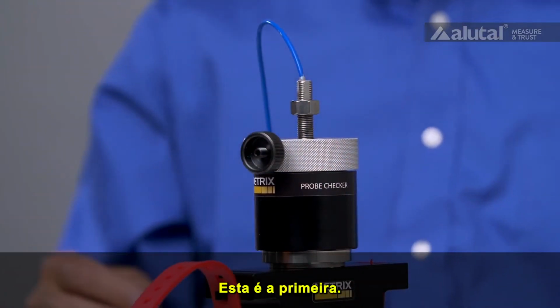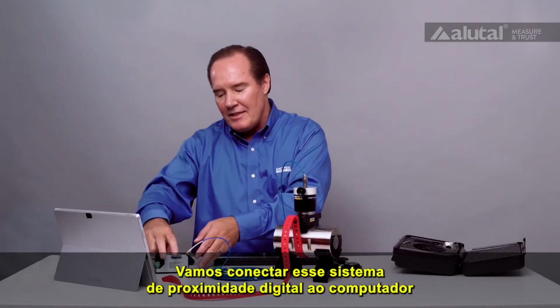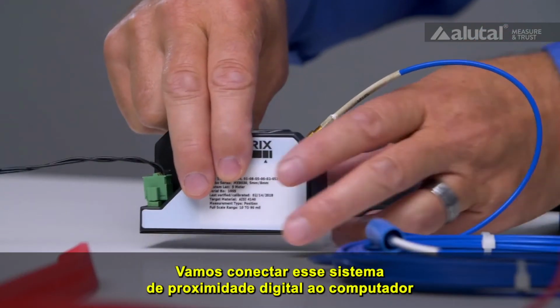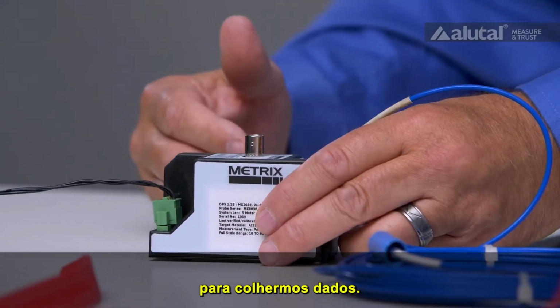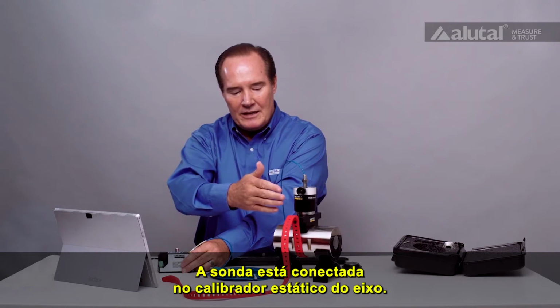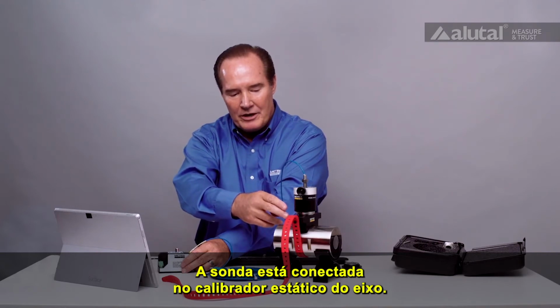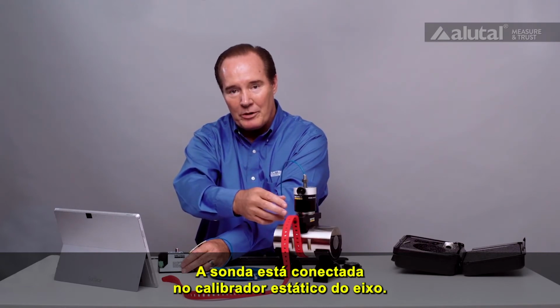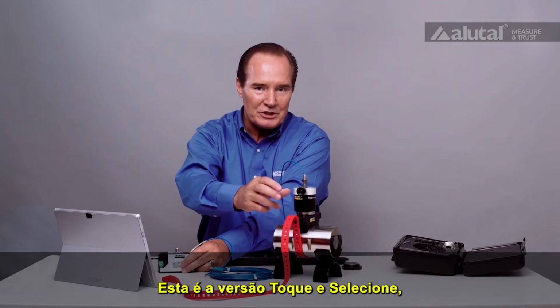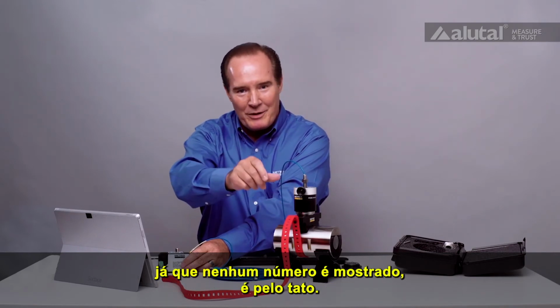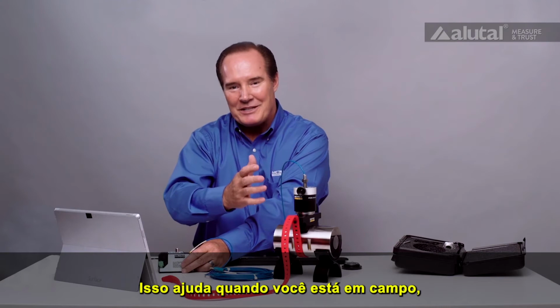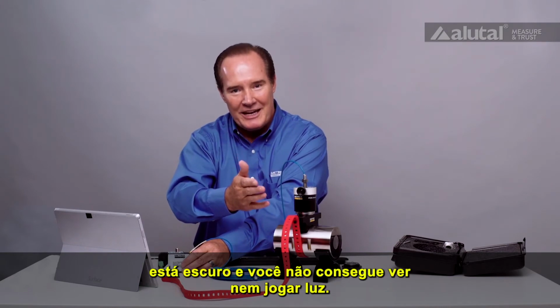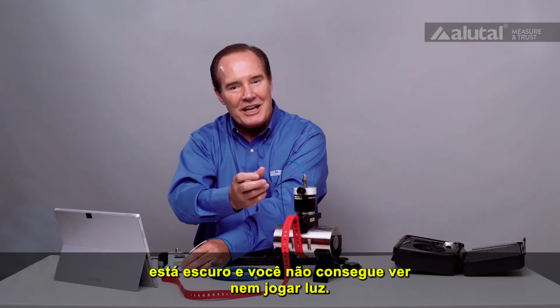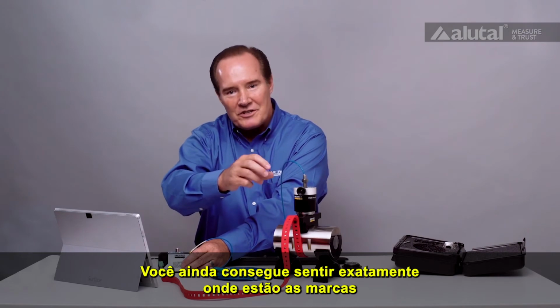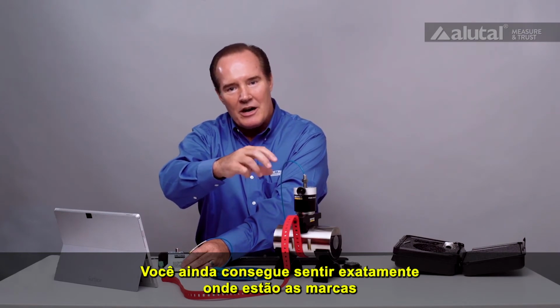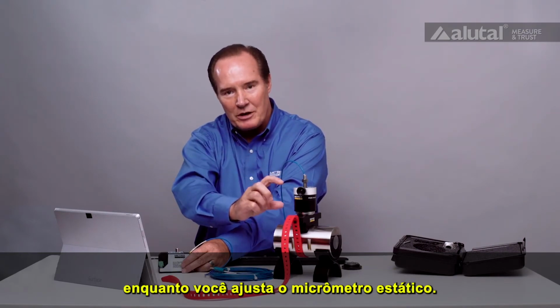That's the first one. Okay, we're going to connect the digital proximity system to the computer so we can take data. So we have the probe set in the static calibrator for the shaft, or the shaft static calibrator. This is the touch select version because there's no numbers coming out of here. It's by feel. You can do that. And it makes sense when you're on site, when it's dark and you can't see and it's difficult to get light in, you can still feel for exactly where the indents are as you adjust the static micrometer.